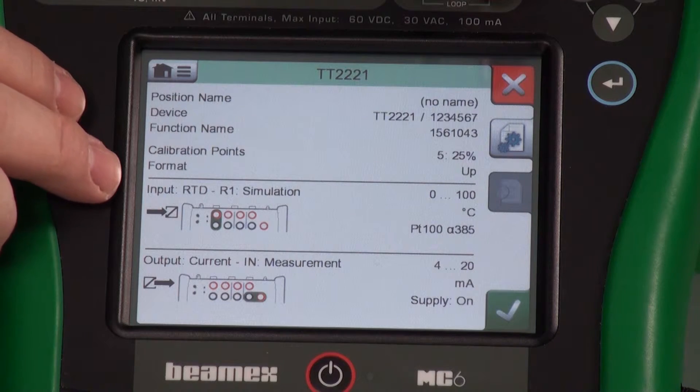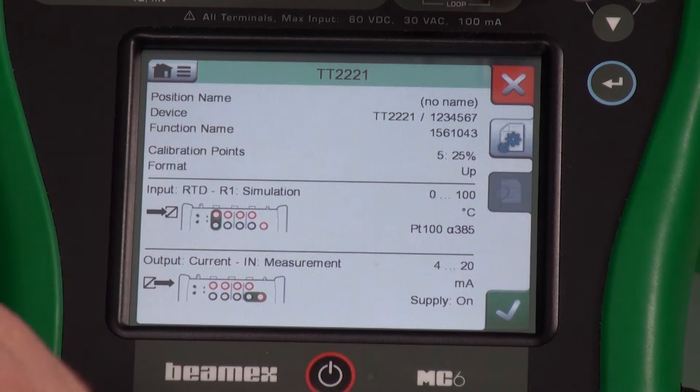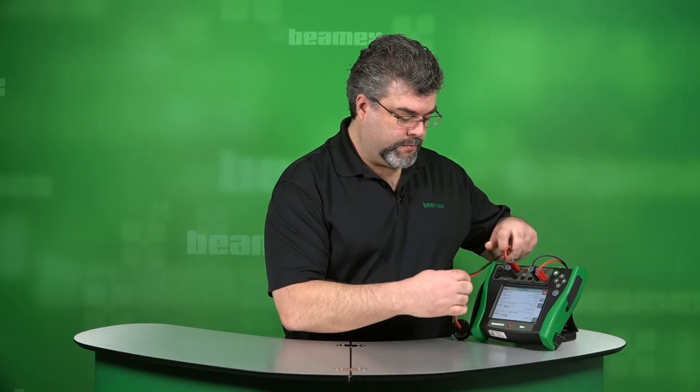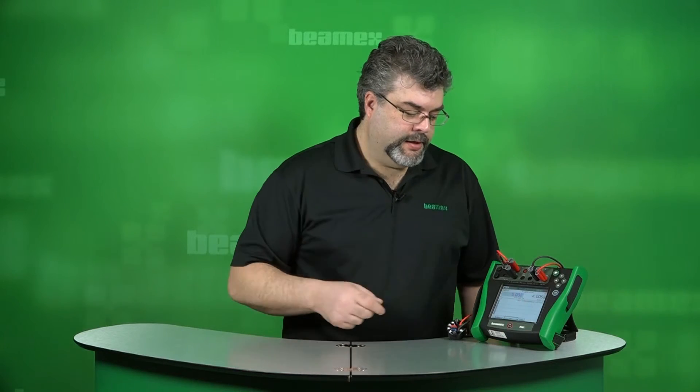This shows us where to hook up the input — it goes right here. So we are simulating our RTD, sourcing resistance to simulate the temperature. Our output is already hooked up — that's right here. By pressing the green check mark, we're in our calibration screen. Now it's waiting for me to press start. But before I do that, let me just cover a couple things.